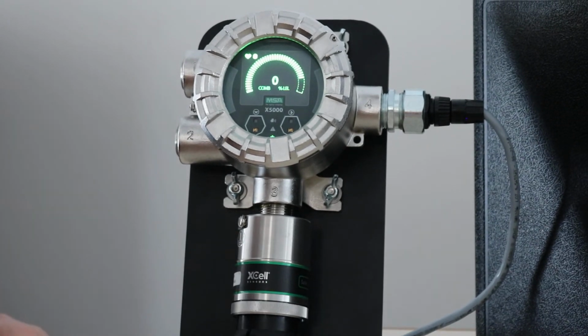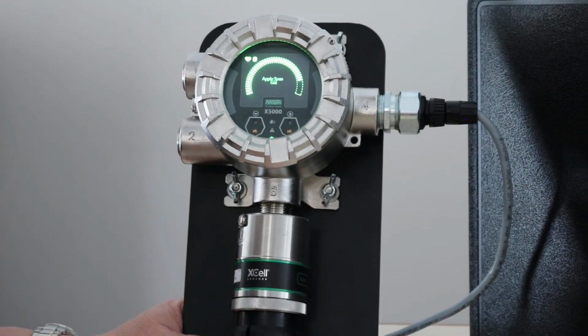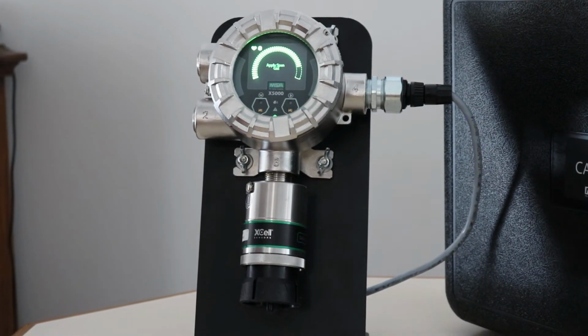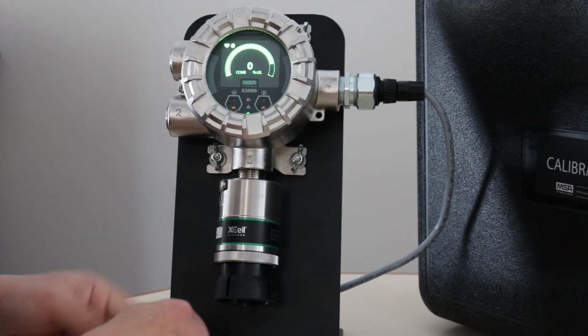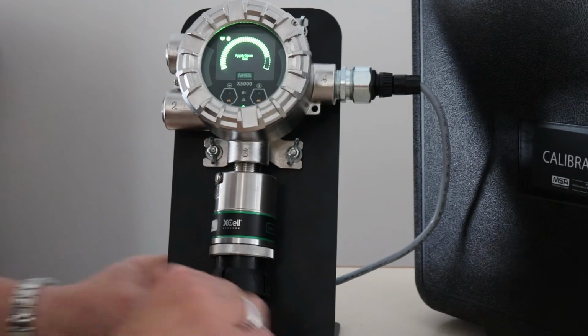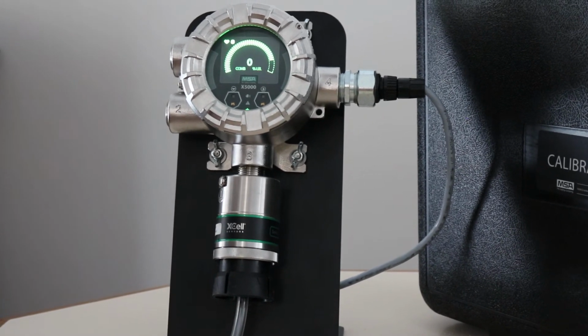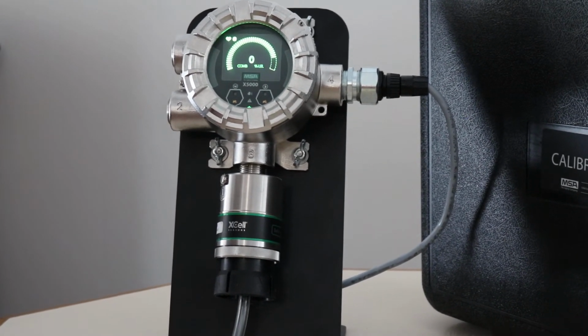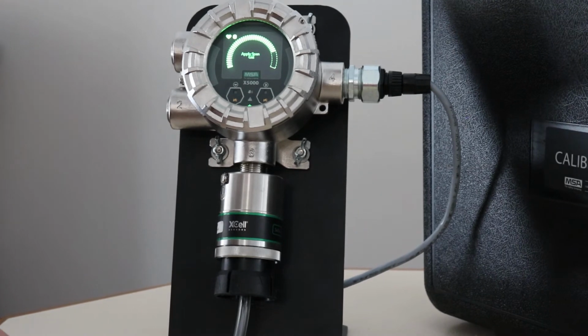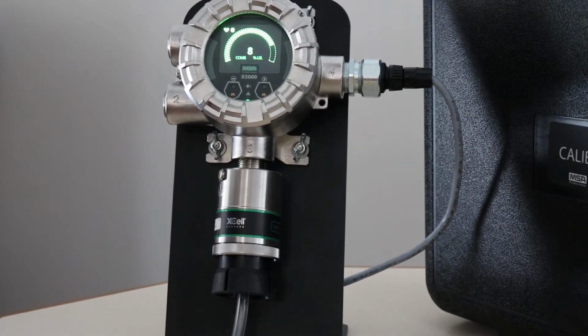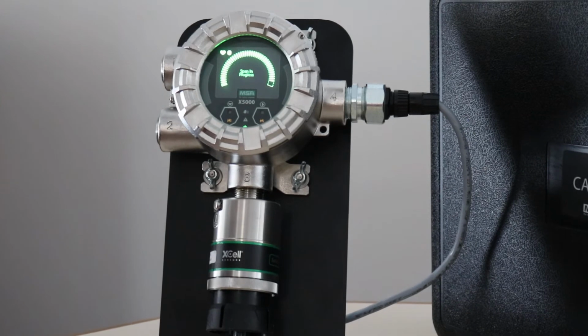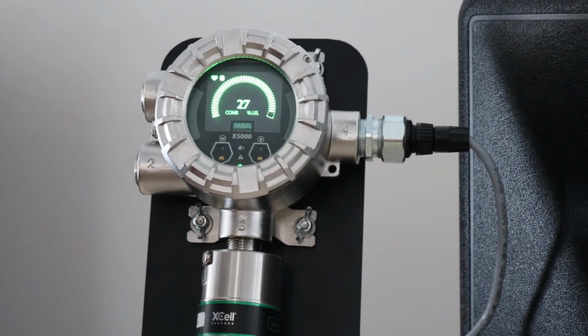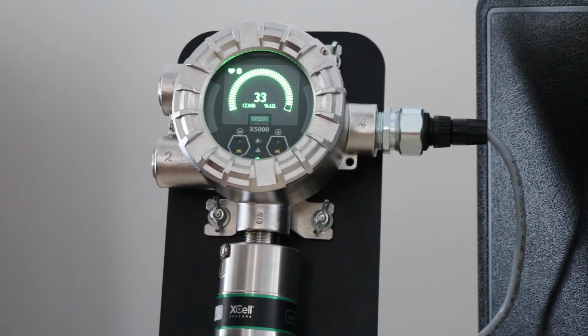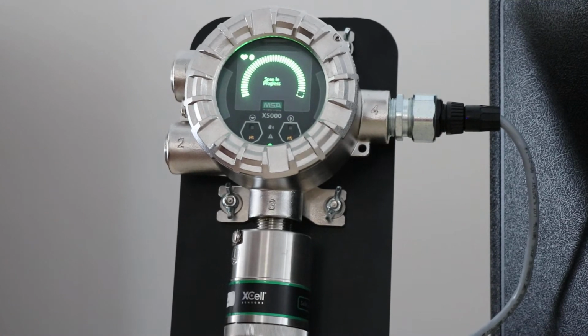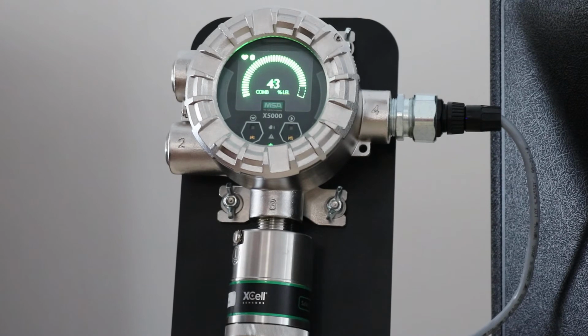Alright, I'll stop there. It says apply span gas, so I will disconnect zero gas. I will slide over our span gas and I will turn that on at the regulator. This is the time that having the separate regulator and separate tubing would be very handy, because otherwise this is the time you will have to unscrew the regulator from the cylinder and hook it up to the span gas cylinder in order to put it on here.